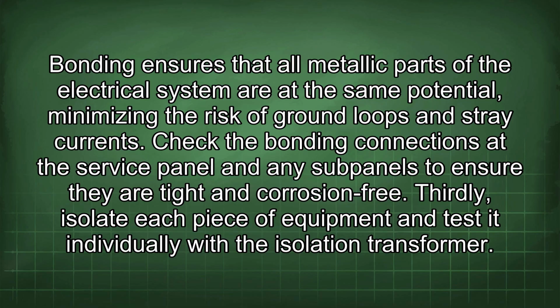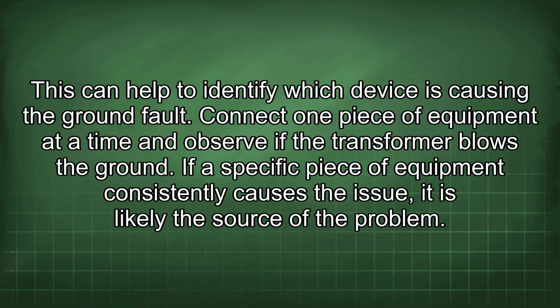and corrosion-free. Thirdly, isolate each piece of equipment and test it individually with the isolation transformer. This can help to identify which device is causing the ground fault. Connect one piece of equipment at a time and observe if the transformer blows the ground. If a specific piece of equipment consistently causes the issue, it is likely the source of the problem.